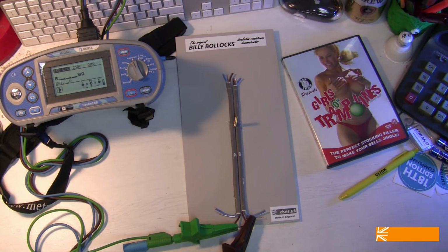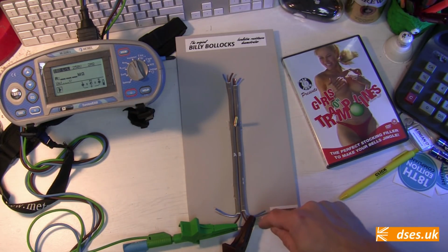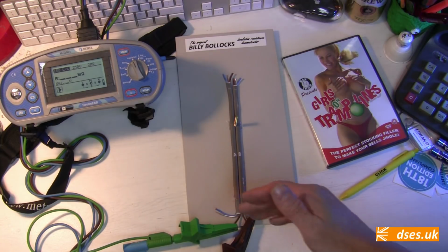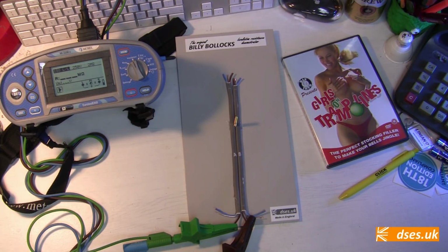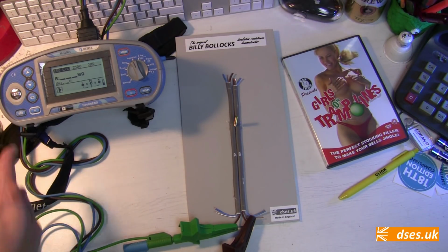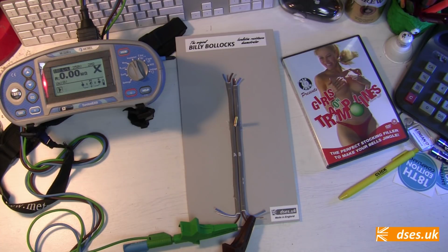My Metrel is going to pump in 250 volts DC on the brown clip, and if these cables were undamaged and in top condition, then nothing would come back on the green clip and we'd have a reading greater than 999 megaohm, which is off-scale high for this instrument. Let's see if we do get that. Nope, that's a fat fucking zero if ever I saw one.